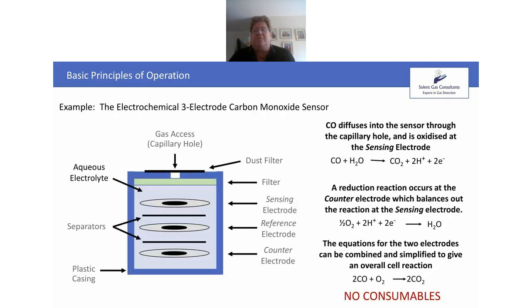And so, in a bit more detail, basically what you've got here is a plastic container with a small capillary hole in the top. Now, this capillary hole, the dimensions and form of this capillary is very crucial. It's critical to the performance of the sensor. It's important that just about enough gas enters the sensor that can be reacted on the sensing electrode, but not too much that the electrode becomes overwhelmed or saturated. On top of this hole, you'll have a disc, typically made of PTFE, which is primarily to prevent dust and dirt from entering the sensor.